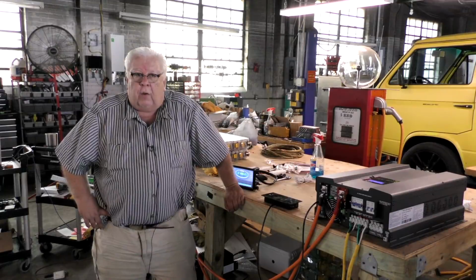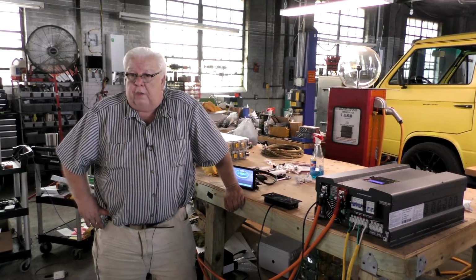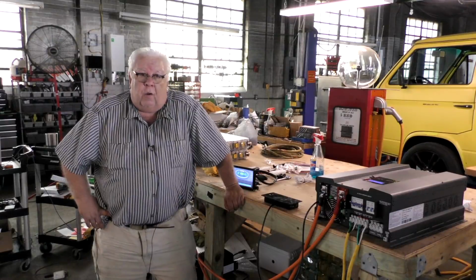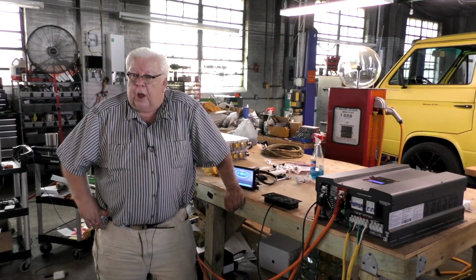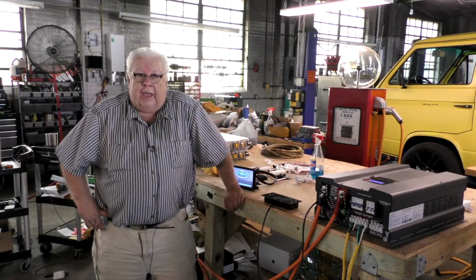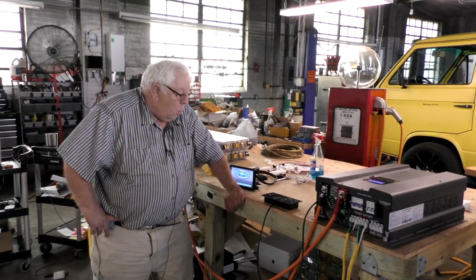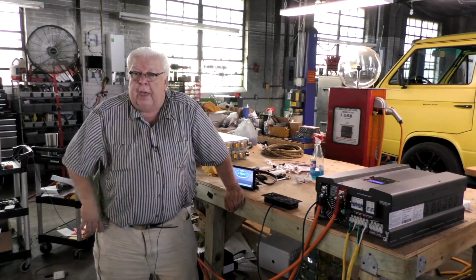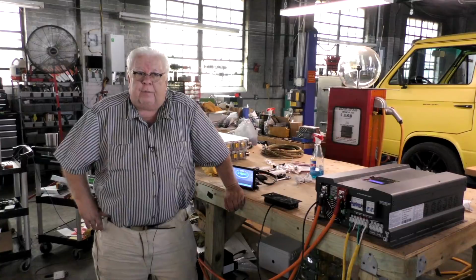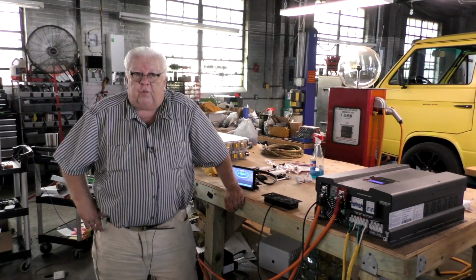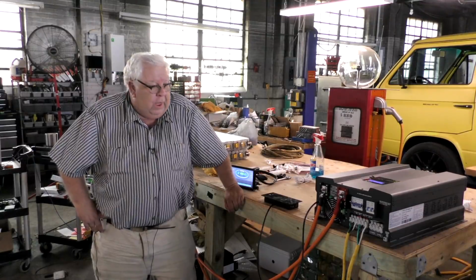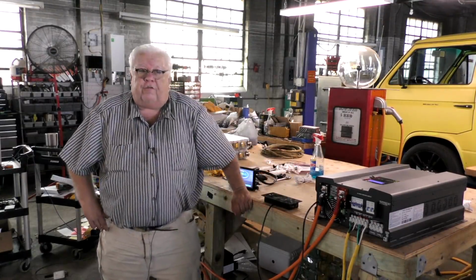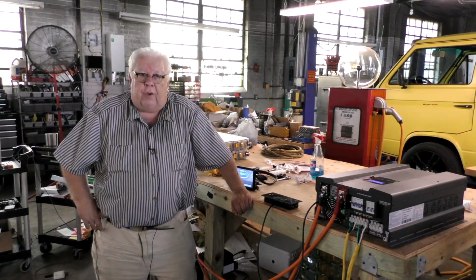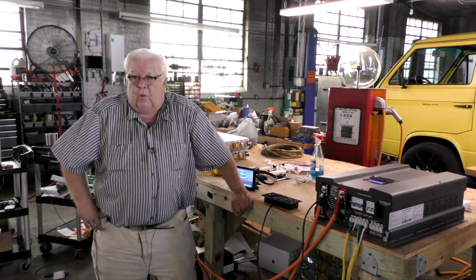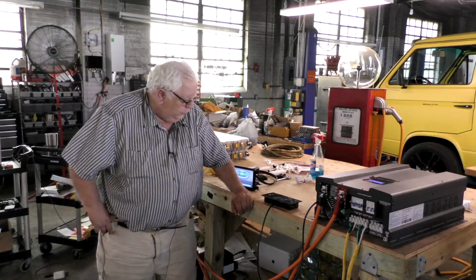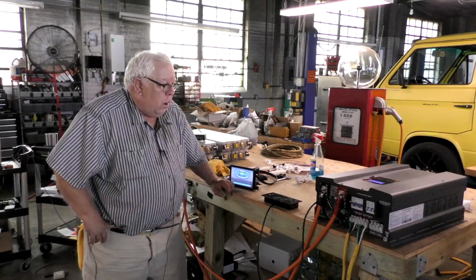selfish solar that only uses the grid when you just ran out of sunshine and battery, or as we say, airspeed, altitude, and ideas all at the same time. And at that point, it'll feed from the grid or a generator, which you can fire up. And in many areas of the world, that's actually more appropriate. And it should be rare enough a situation that a generator would be appropriate. And we actually have a relay output to start the generator when the battery gets down to the low voltage battery alarm, which we've measured at about 39 volts. And so that's what's going on with this inverter.